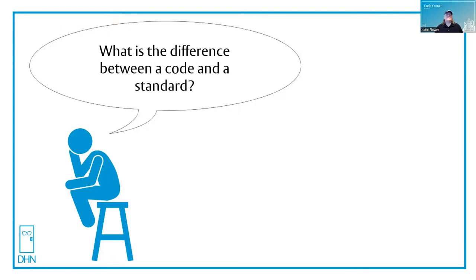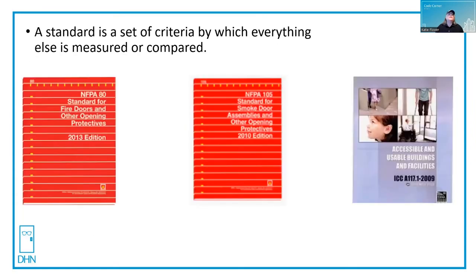That's a great question, and one I get very often. A standard is a set of criteria by which everything else is measured or compared. We use many standards in this industry. One of them is NFPA 80, the standard for fire doors and other opening protectives. The standard doesn't tell me where I need to use a fire door or what the rating needs to be, but it does tell me if you need a fire door, it needs to look like this and act like this, and the hardware requirements are as follows.